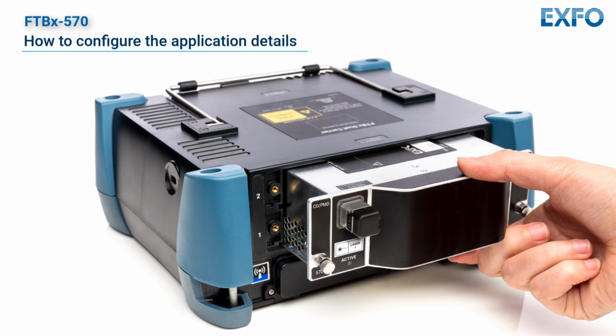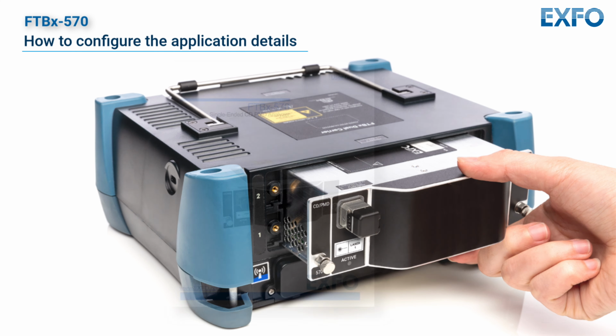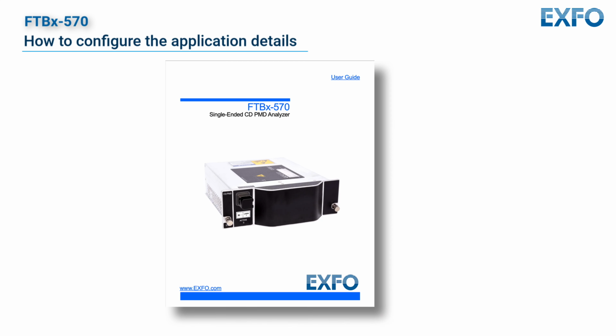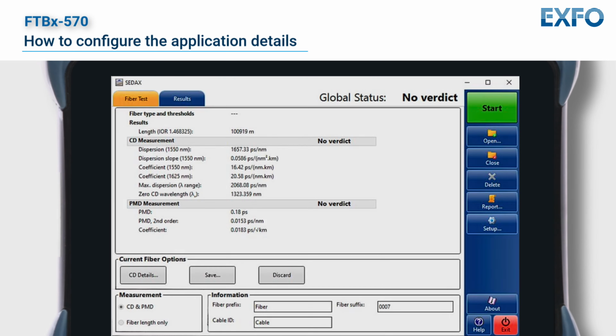The many features of the single-ended CD-PMD analyzer are controlled by the Windows-compatible software installed on the platform. Please refer to your platform's user guide for more information. The parameters you set will be kept in memory after turning off the platform. To configure the application details, from the button bar, tap Setup.